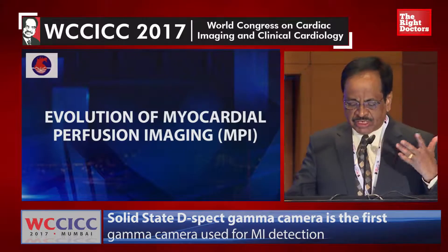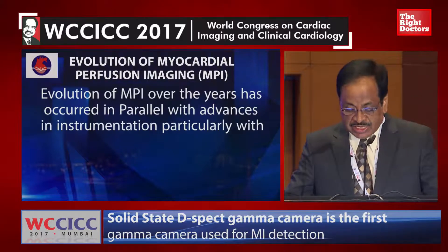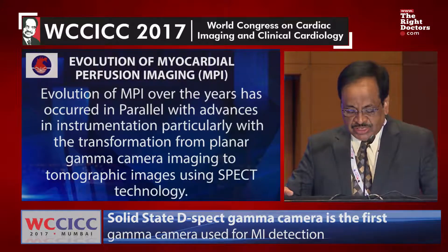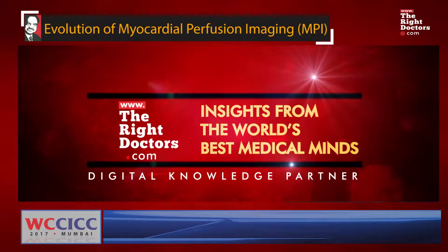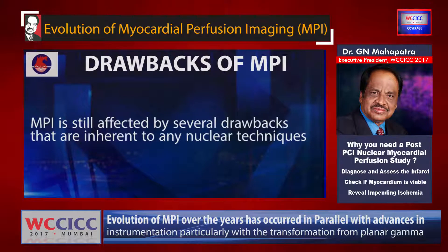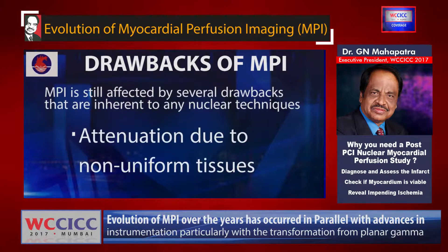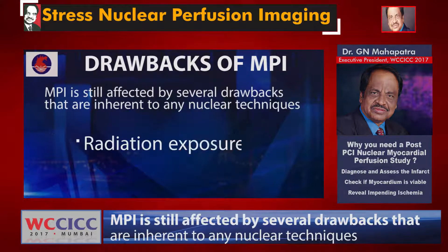Myocardial perfusion imaging has evolved over the years in parallel with advances in instrumentation, particularly with the transformation from a planar gamma camera to SPECT technology, and then to gated acquisition for combined assessment of myocardial perfusion and left ventricular function. The drawbacks of MPI include low photon flux, attenuation due to non-uniform tissues, motion artifacts due to time-consuming scans, and of course radiation exposure.